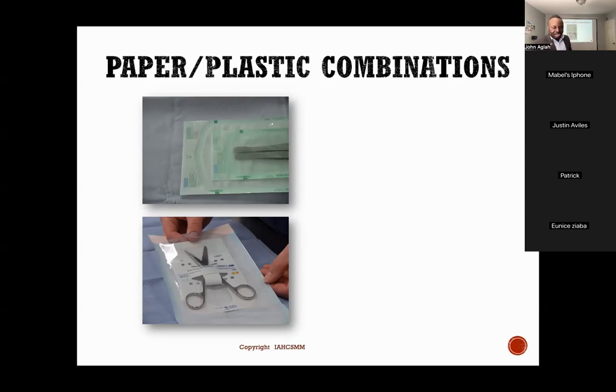Let me come back to this. What you see right there is a tamper lock. It is a tip protector, which also serves as a medium that helps the instrumentation stay open during sterilization and even afterwards. When we open it this way and put it in the peel pouch and seal it with a chemical indicator, after sterilization and multiple handling, this closes by itself.